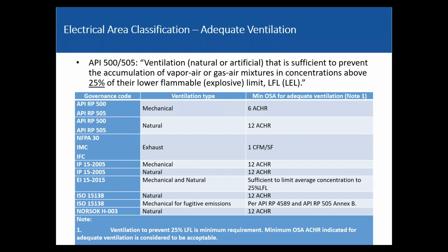There are a couple of calculations in the back of 505, I think it is, and they talk about how big your openings have to be with respect to temperature gradients, and then wind, and what percentage of the time. You look at the max wind, and I think they give guidance on the percentage of that you can take. It's like the lower 48 gas fields, where you have compressors that are enclosed because residents don't like what they look like, gas compression in the countryside of Colorado. There's a lot of natural ventilation there.